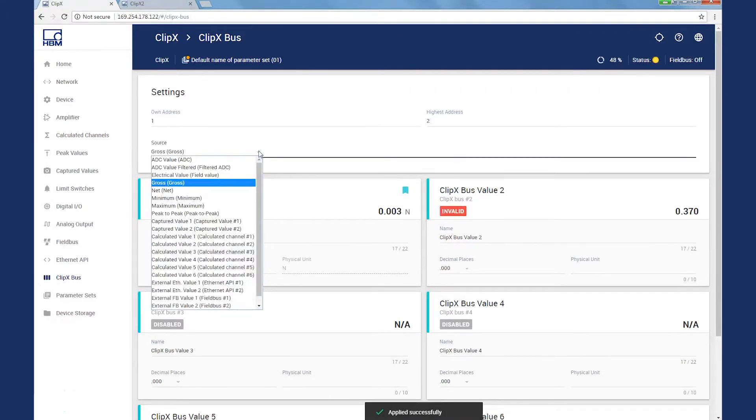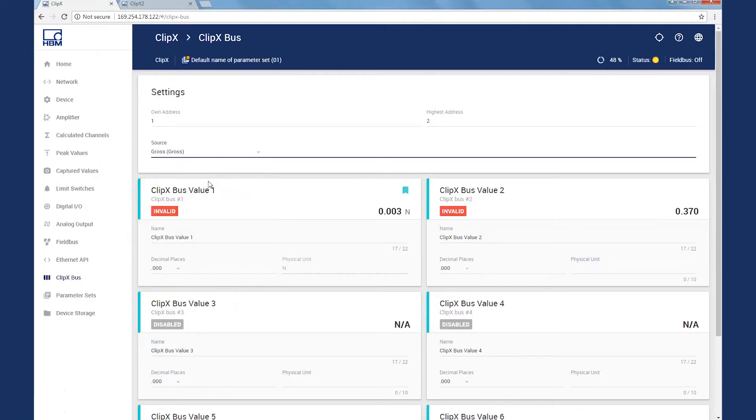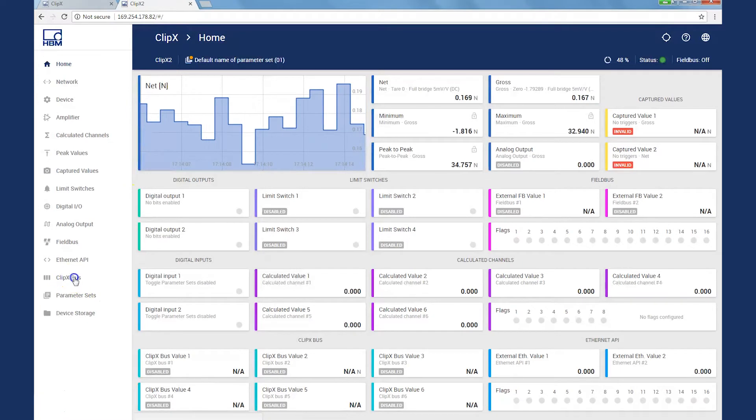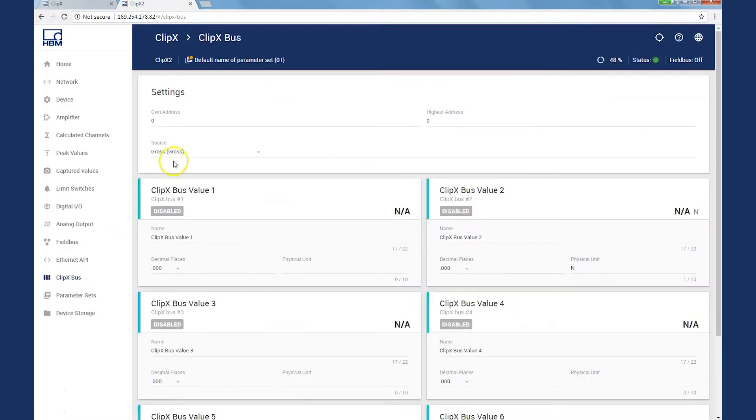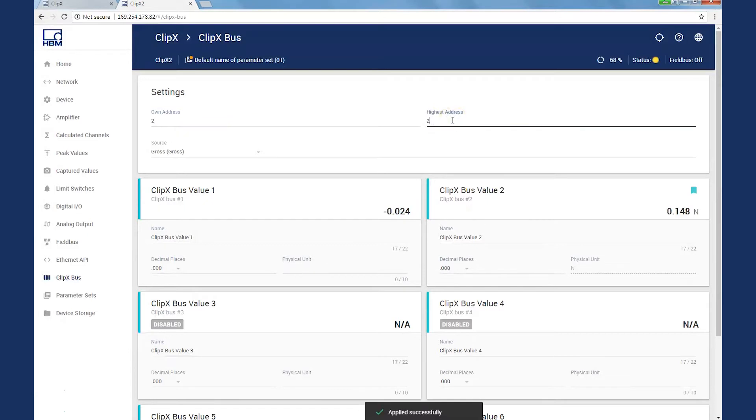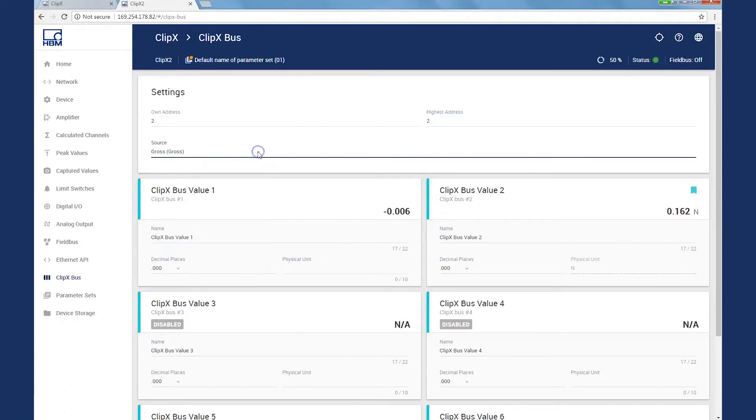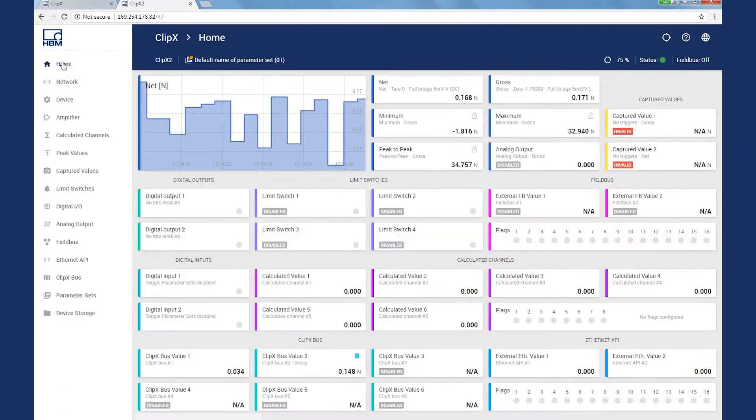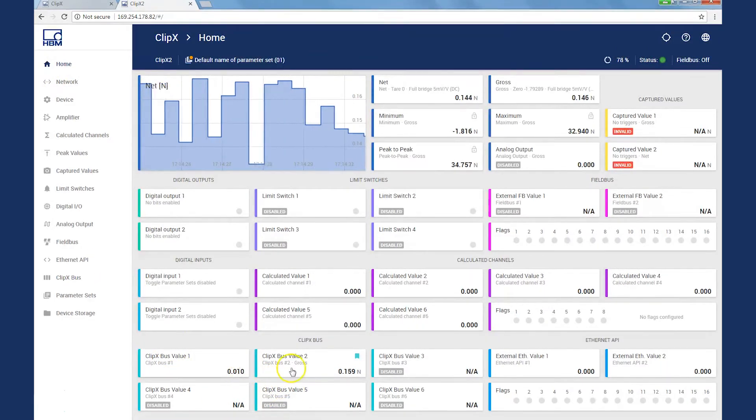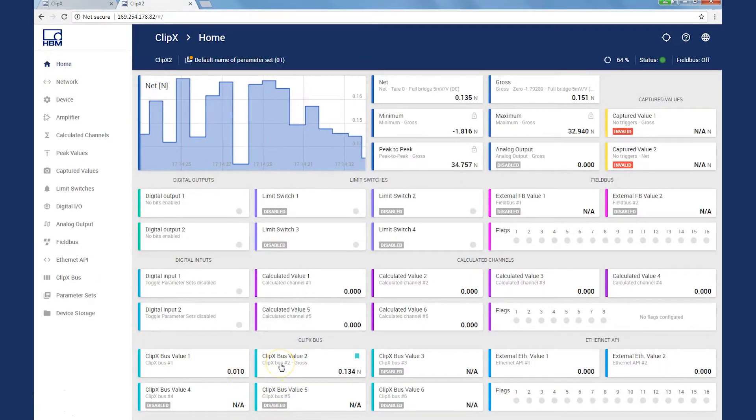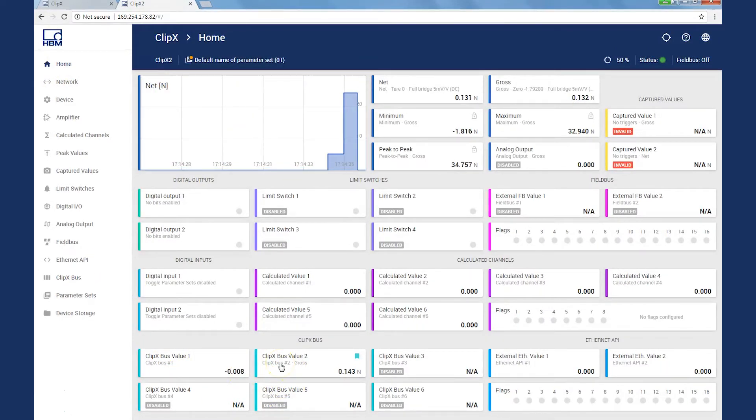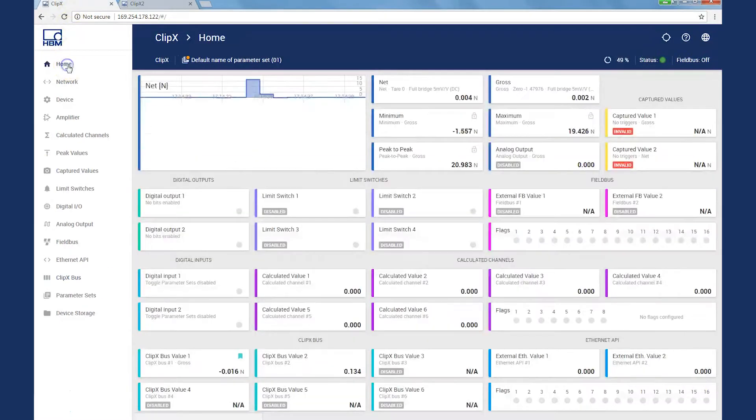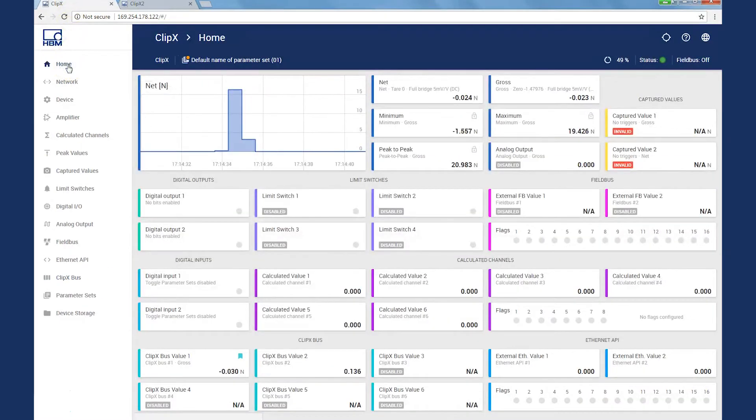Each device can put one signal onto the ClipX bus, so I select the gross signal for the first and then do the same for the second device. In the menu ClipX bus, select your own address, which in this case is 2, and the highest address for two devices is also the 2. Again, the signal is the gross signal that we introduce for the ClipX bus, and when we switch to the home view, we immediately observe the values on the ClipX bus of our two measuring amplifiers. The same applies to the view of the first device.